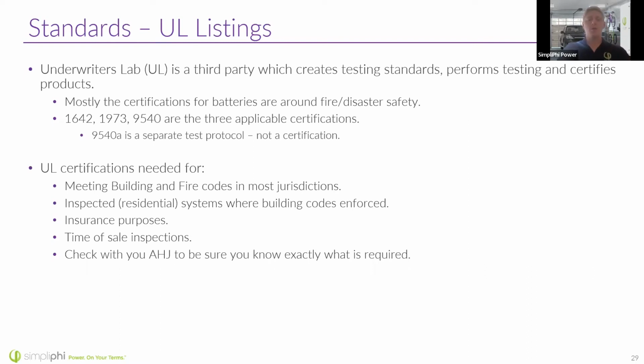So for those of you who are familiar with lithium iron phosphate, it's a very safe, inherently thermally stable product. So this 9540A forced thermal runaway event was extremely uneventful. Whereas a lithium cobalt oxide battery would easily catch fire in a thermal runaway event, lithium iron phosphate barely reacts at all, which is a nice reassuring thing for you installers and homeowners to understand. Regardless though, be sure to check with your AHJ so you understand what UL listings and what building codes you have to meet.